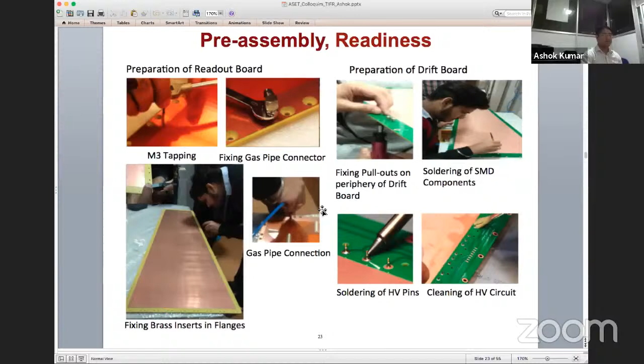Then we go for assembly and stack preparation, a stack of 3 foils along with the 2 electrodes. We go to the clean room, class 100, and do the assembly of these detectors. You can see that there are different steps involved, and we prepare a detector. In the bottom, you can see two students handling a detector. We have fabricated a detector, and it took almost 4 to 5 hours in a clean room. It is a very delicate process, because if any dust particle enters the gas volume, it will create discharges, and then the detector will not qualify for its use.